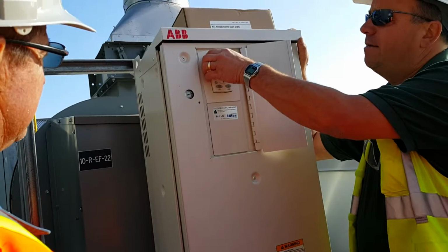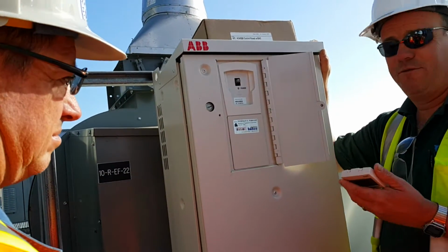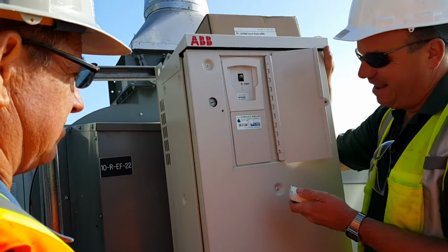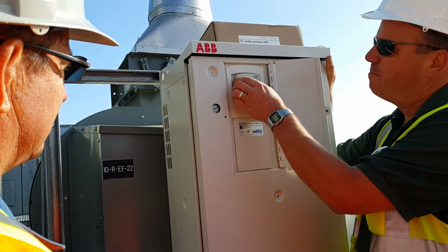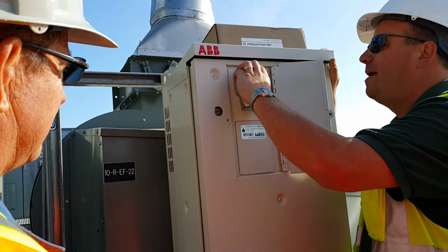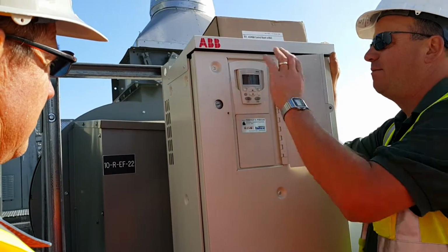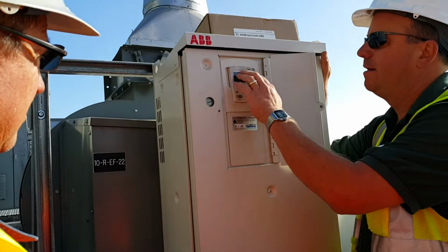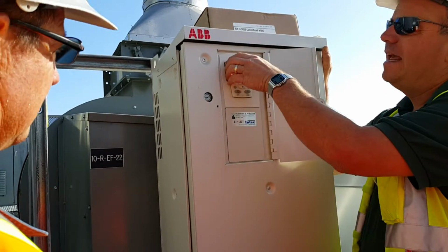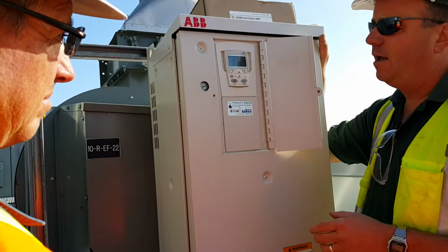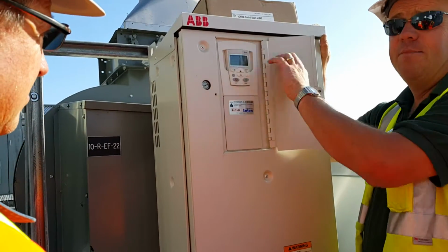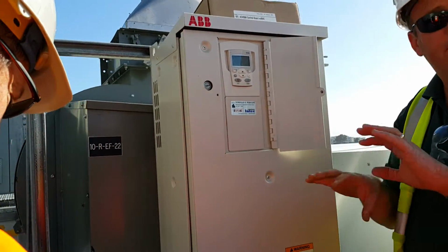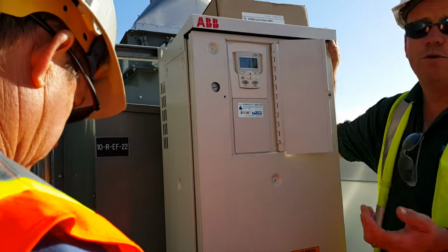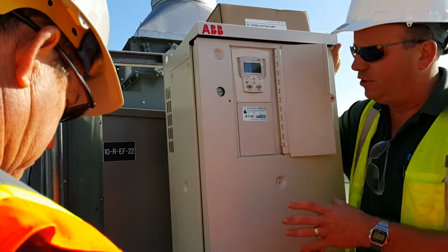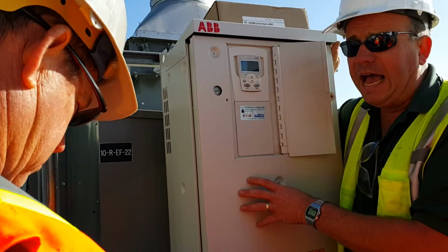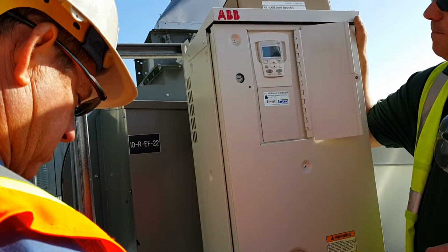You got a removable keypad right here. Be very careful when you remove it. The best way to remove it and put it back in is to get a good feel for it in there before you force it in. Sometimes we'll pop that board back and it'll go right in. You can take this out anytime, even while it's running. It's not going to shut anything down. You can also take this keypad and bring it to another drive if you're trying to do any troubleshooting, by swapping keypad. It won't change the program. It won't make any different changes. The program resides inside the VFD itself.